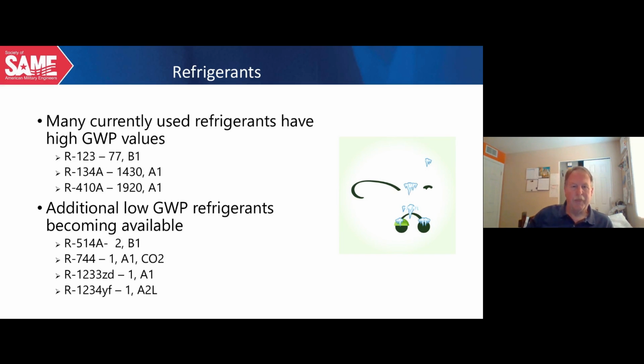Now, refrigerants that are currently available that are low GWP and will become available in the relatively near future. Low pressure refrigerant, which would be a replacement for 123, would be R514A, has a global warming potential of 2 and is a B1 refrigerant. CO2 is actually a refrigerant. It's used relatively sparsely, especially in the United States. One of the issues is because of our ambient temperatures, you get really, really high condensing pressures. So it tends to be used in Northern Europe a lot, or areas of the world that are relatively cold.